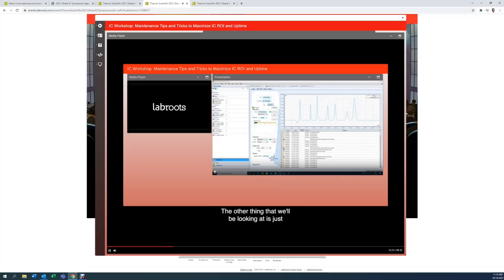The other thing we'll be looking at to make sure the instrument is performing is the pressure. The pressure in this instrument is running around 2,000 psi, and the important thing here is that it's stable. It's not bouncing up and down by several hundred psi. Again, if you don't see a stable pressure, you won't see a stable baseline. If you don't have a stable pressure, more often than not it's because you have a bit of air in the pump. You just need to prime the pump out. So that's the basic chemistry.